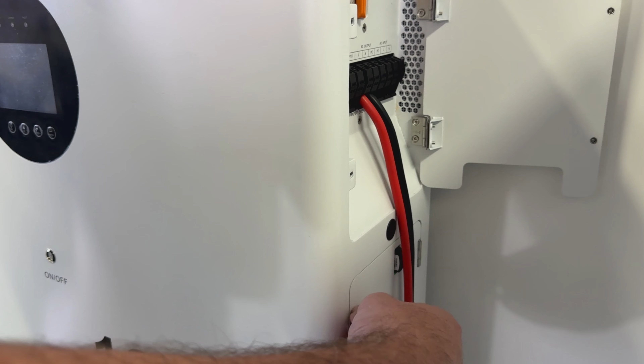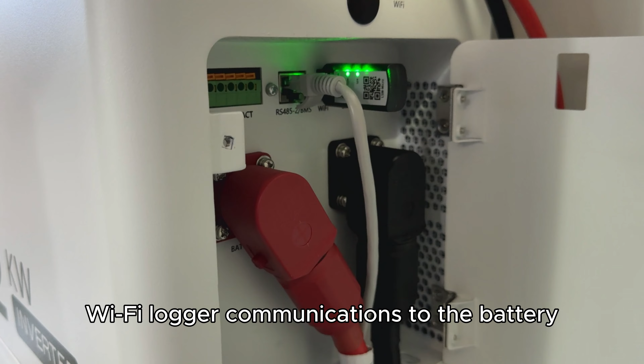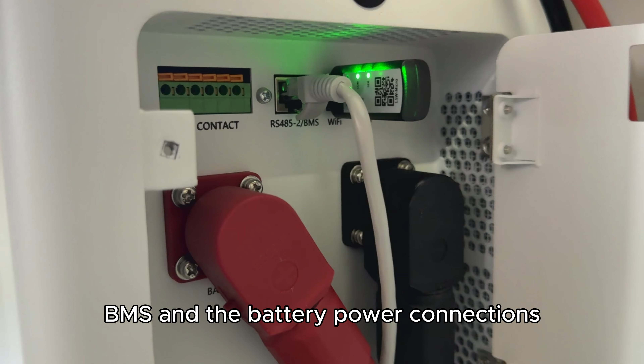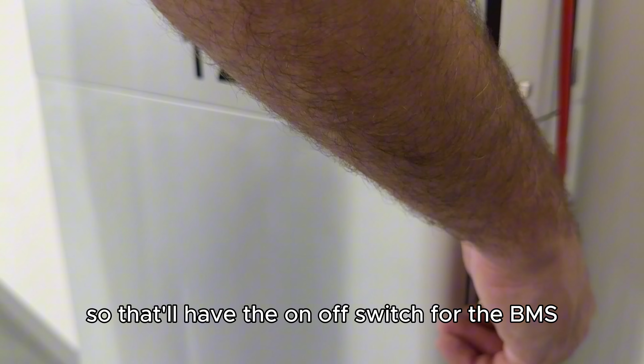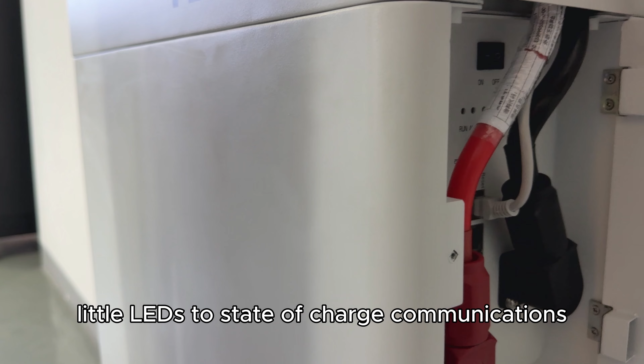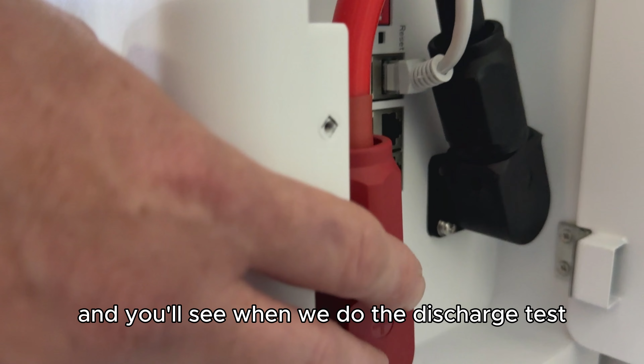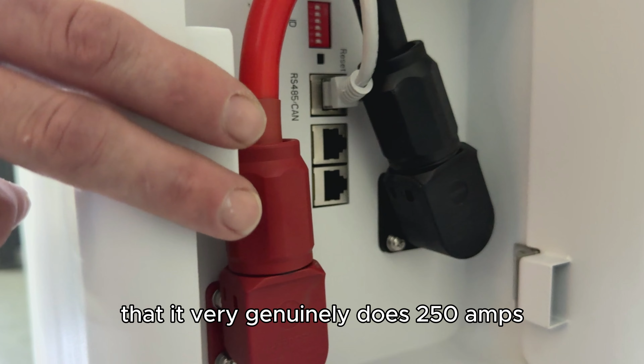Under the next cover is where you've got some communications. So you've got the internet Wi-Fi logger, communications to the battery BMS, and the battery power connections. And then under the next cover is the battery side. So that'll have the on-off switch for the BMS, little LEDs for state of charge, communications, and your battery connections. Each of those connections is rated for 250 amps, and you'll see when we do the discharge test that it very genuinely does 250 amps.